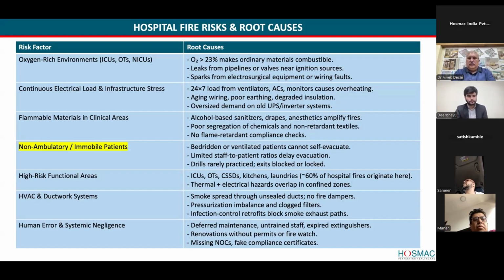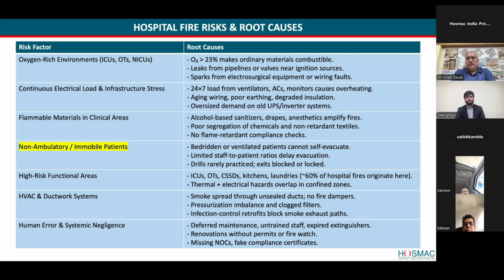That is one thing. And nowadays, the CFO also insists on makeup air. So the idea is that the makeup air has to be supplied from the bottom level, up to the 1 feet level, so that whenever occupants are passing through an escape passage, they get oxygen. Because in smoke, everybody knows that it generates carbon monoxide and carbon dioxide. So it causes suffocation problems while escaping. So the idea is to provide oxygen from the bottom, so that people can easily go through the smoke area and get out of the building.